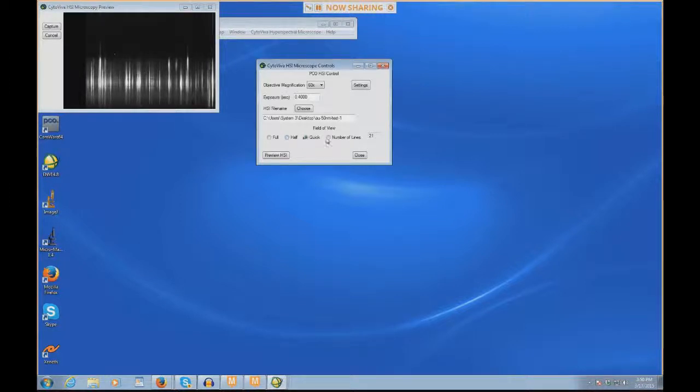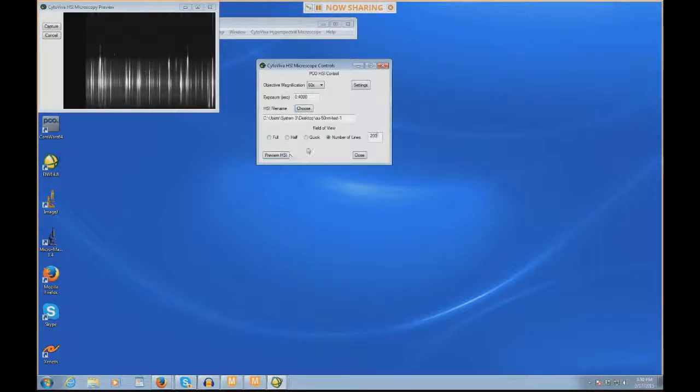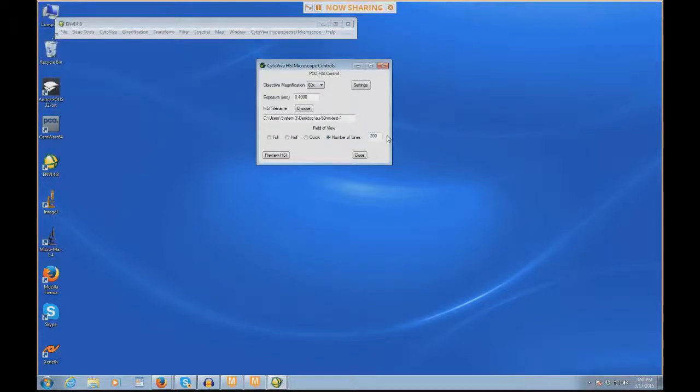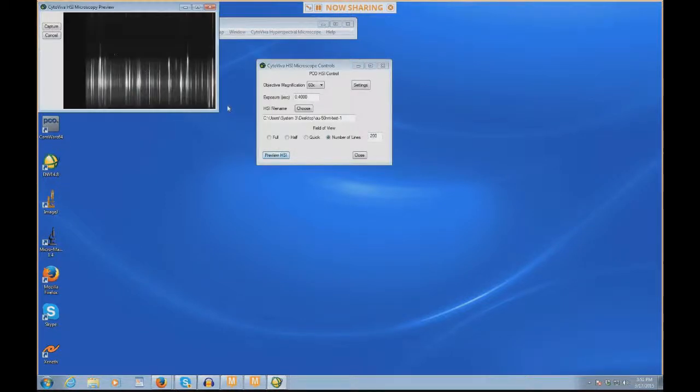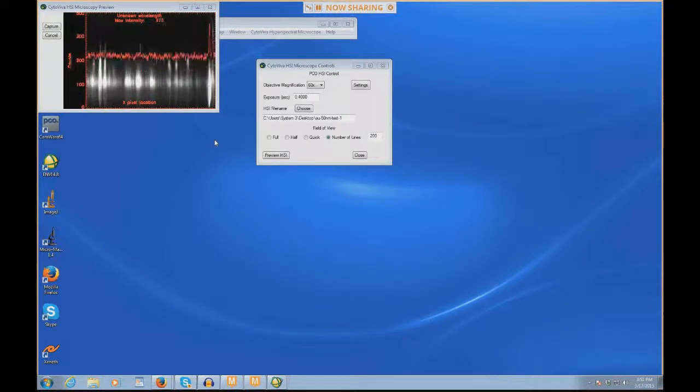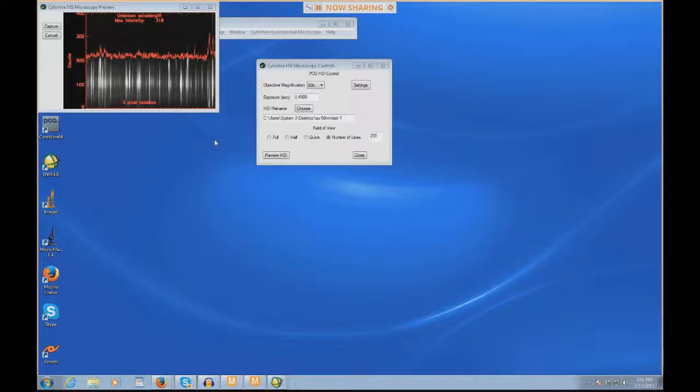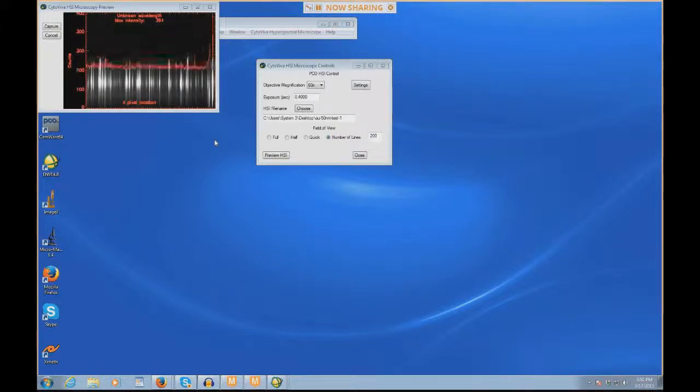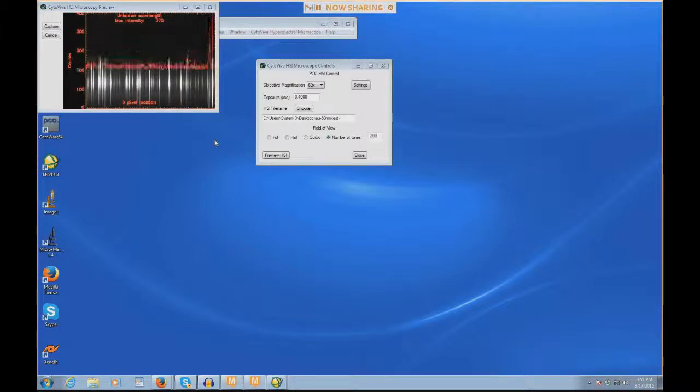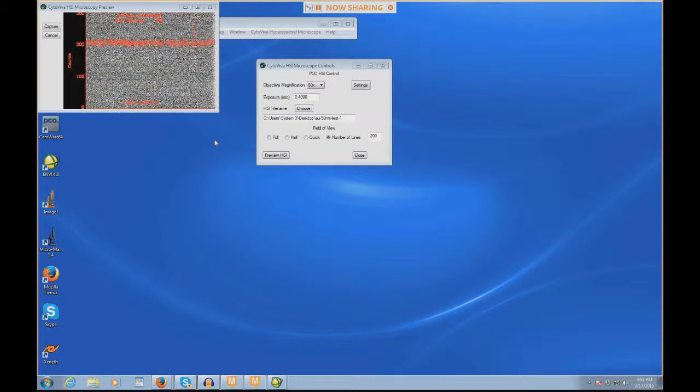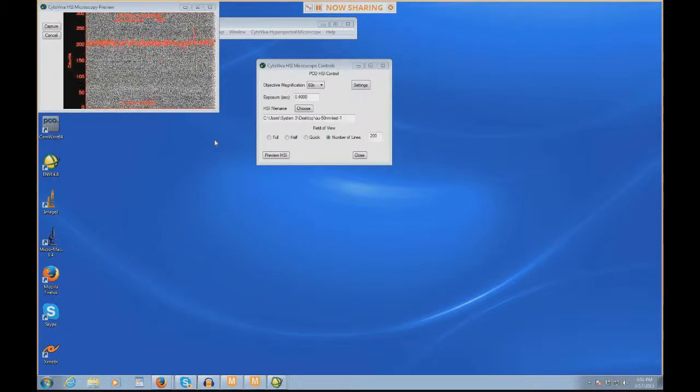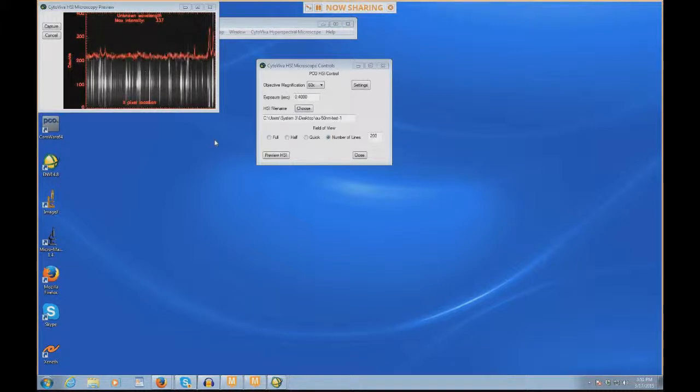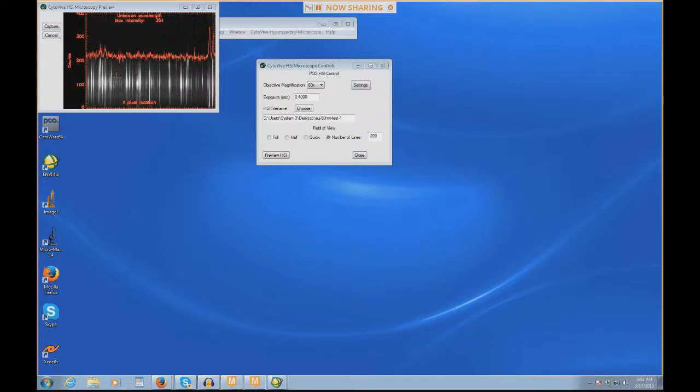I'm going to demonstrate that here. I'm just going to do number of lines. I'm going to do just a couple hundred lines. I'm going to keep this exposure time. It's important to note that when you change your exposure time and when you change the number of lines or change your field of view, you have to hit cancel for this to auto-update. Now I'm going to hit preview again, and these particles look like they're in focus. I'll throw them out of focus and then back into focus here. If you're in focus in the eyepiece of the microscope, it's going to be in focus in the scan. These particles looked in focus. So I'm going to go ahead with the scan. Instead of cancel, I'm going to hit capture.